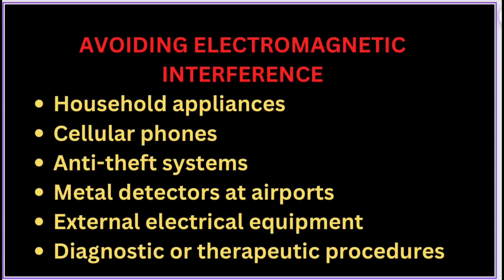Anti-theft systems. Electromagnetic anti-theft security systems are often found in or near the workplace, at airports, in stores, at courthouses, or in other high-security areas. Although interference with a pacemaker is possible, it is unlikely that any clinically significant interference would occur with the transient exposure associated with walking through such a field. Based upon several studies and observations, experts advise that patients with pacemakers should be aware of the location of anti-theft systems and move through them at a normal pace. Avoid leaning on or standing close to an anti-theft system.